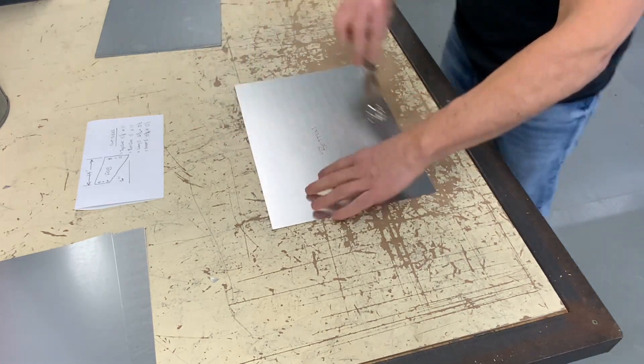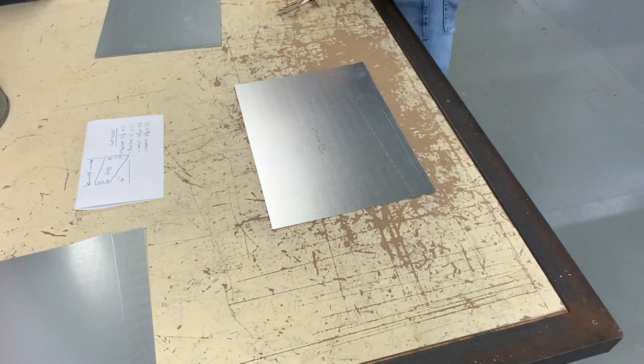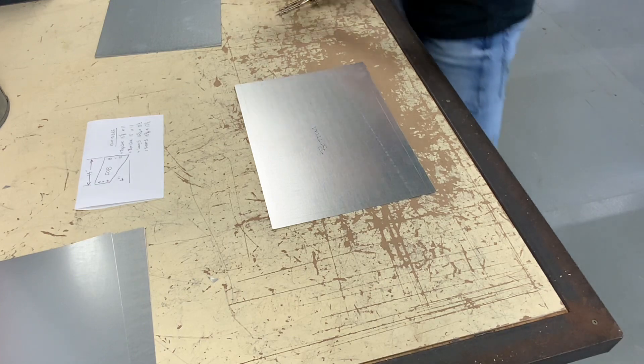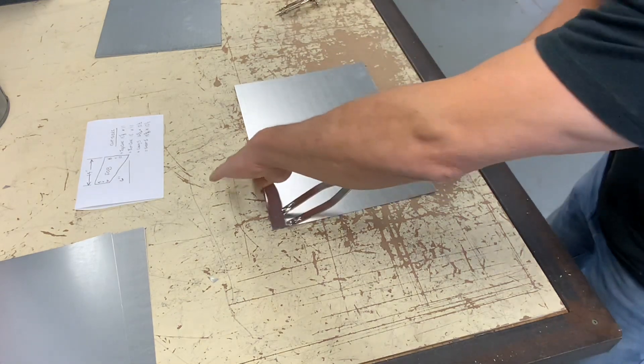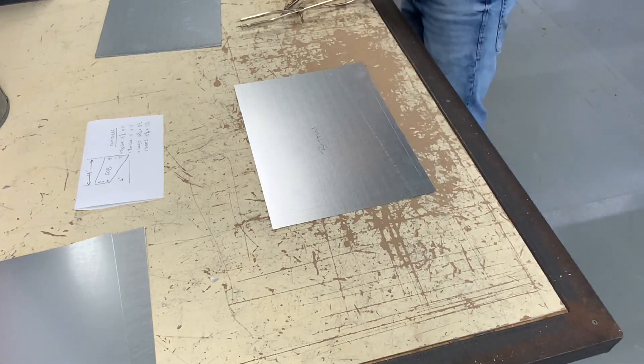I have chosen to put a snap lock, so I'm allowing a half inch for the male part of the snap lock. And now I will scribe the one inch working line for my S and drives.